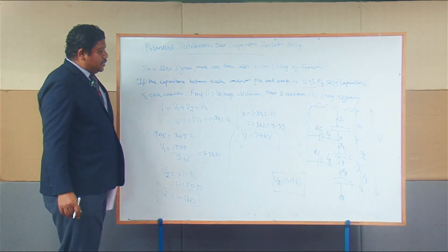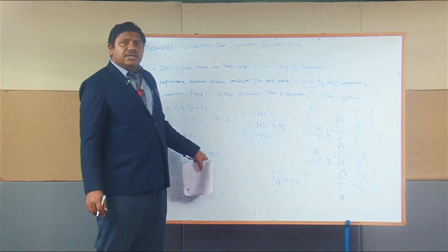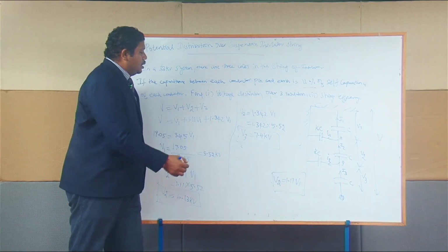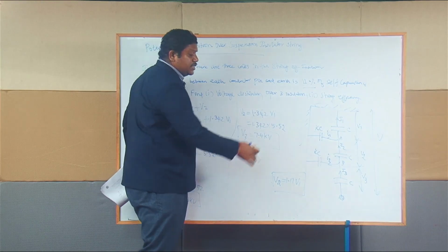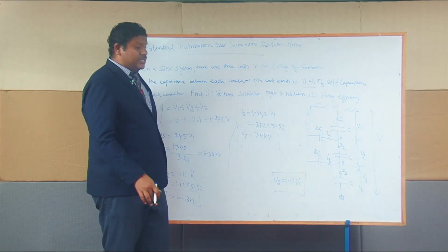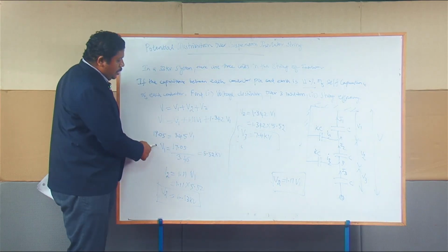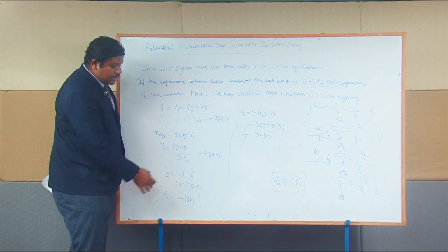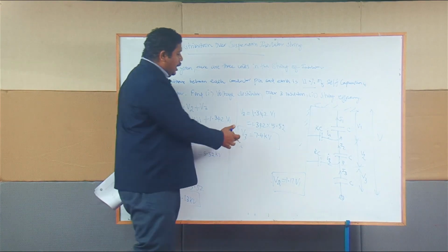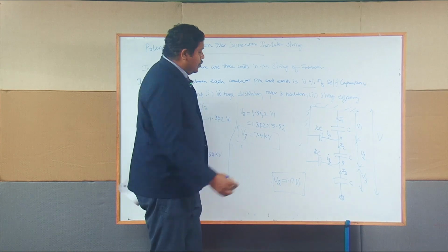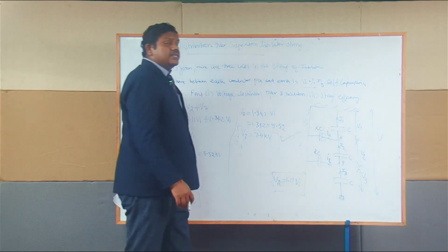So now from this solution itself, we can conclude that the voltage across the last disc, which is nearer to the conductor, is having higher stress. You can see the values: V1 is 5.5, V2 is 6.13 and V3 is 7.4. So V3 is under higher stress.